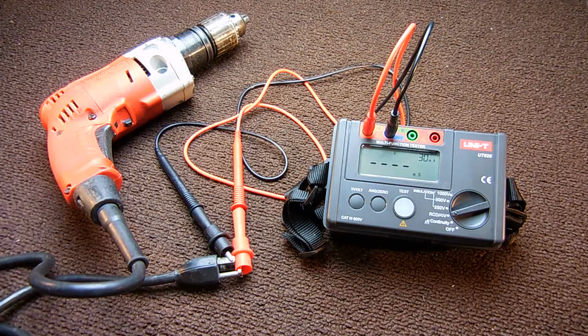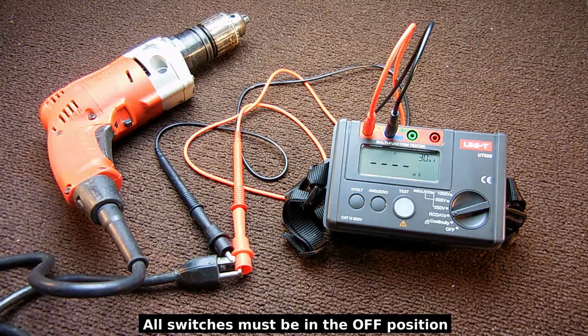If you have a GFCI, ground fault circuit interrupter, on that circuit, you're going to have to remove it from the circuit. You don't have to disconnect the entire thing. You can remove just one side, the hot or the neutral, just as long as it's no longer connected to the circuit, creating a loop. Any dimmer controls, any timer controls, they also must be removed.